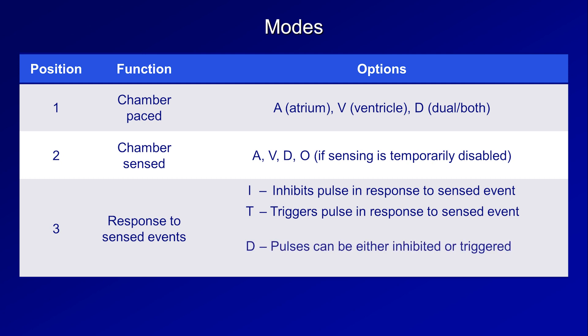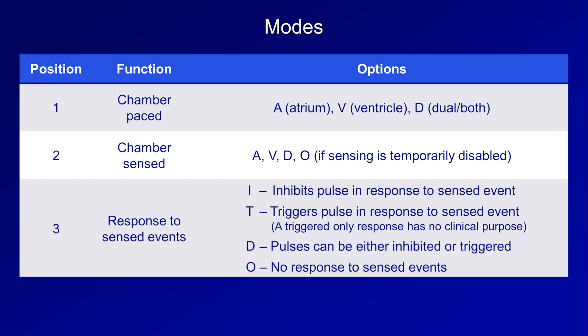The third position is the tricky one — it describes what the pacemaker's response is to sensed events. Options include I for inhibiting a pacemaking pulse in response to a sensed event, T for triggering a pulse in response to a sensed event, D for when pulses can either be inhibited or triggered, and O if there is no response to sensed events or if sensing is disabled. Notably, T — a triggered-only response without any inhibition — has no clinical purpose and should never be used in practice.